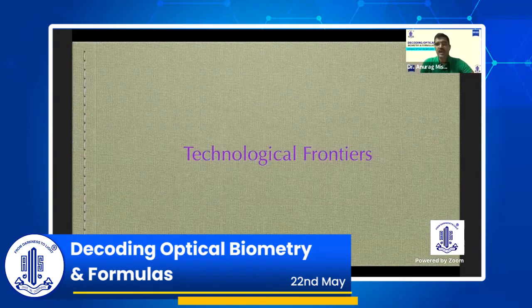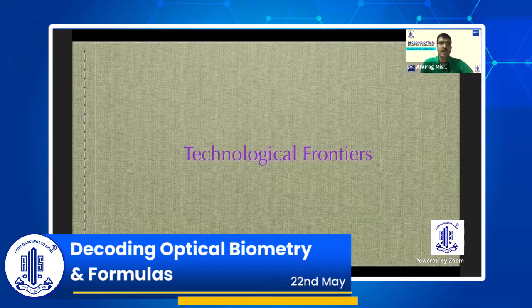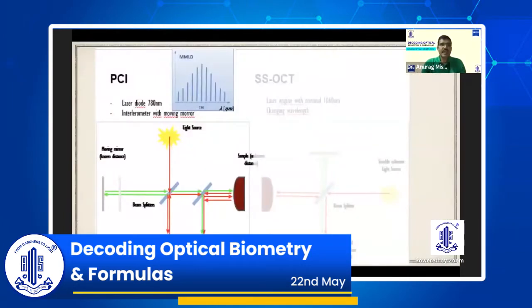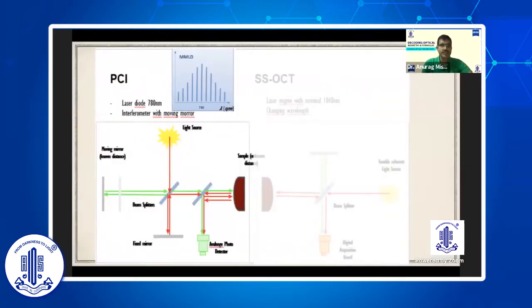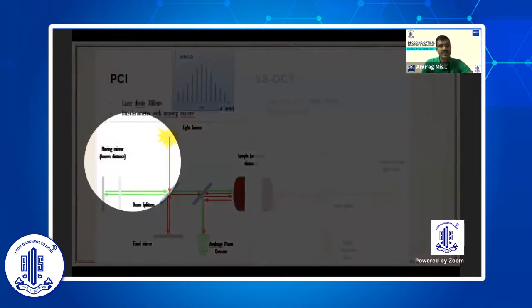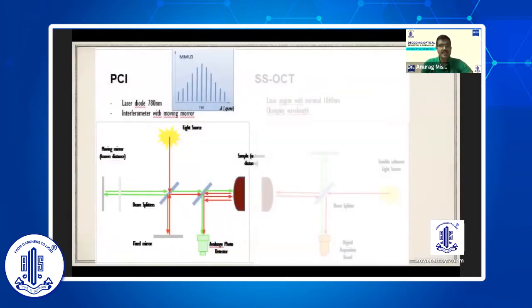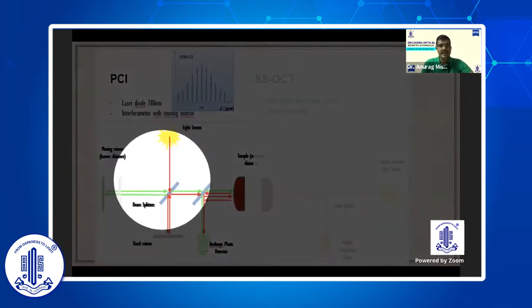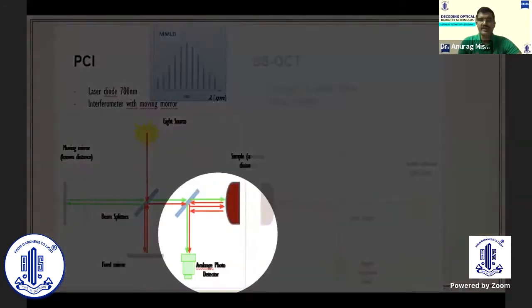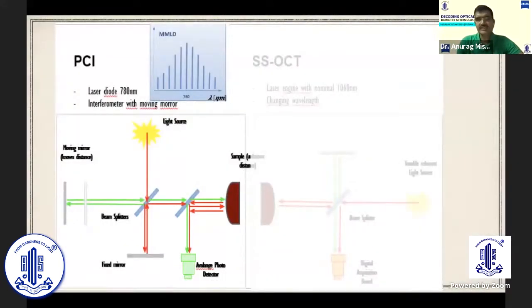The first biometer that ever came into the market, and Zeiss has to be credited for bringing it to our notice, was based on the technology called partial coherence interferometry. It utilized a light source called MMLD, Multi Mode Laser Diode. As you can see, the wavelength is peaking at several points with a gap in between them. The wavelength was 780 nanometers. And this is the only concept which utilized two mirrors. One of them is a moving mirror, the other is a fixed mirror. The light source emanates light which gets reflected, which gets divided by a beam splitter into two halves. Both the light fragments then enter the subject's eye, then they get reflected by another angulated beam splitter to be caught by a photodetector device to give us the reading of different distances between different tissues.